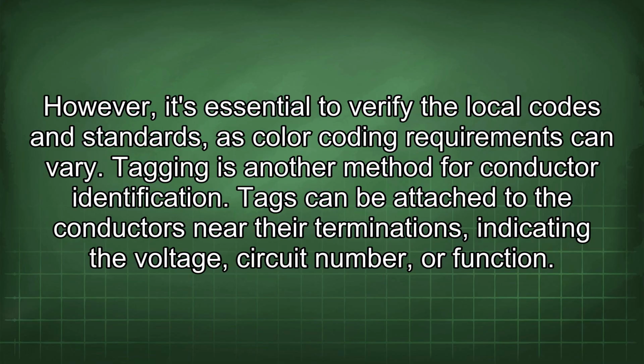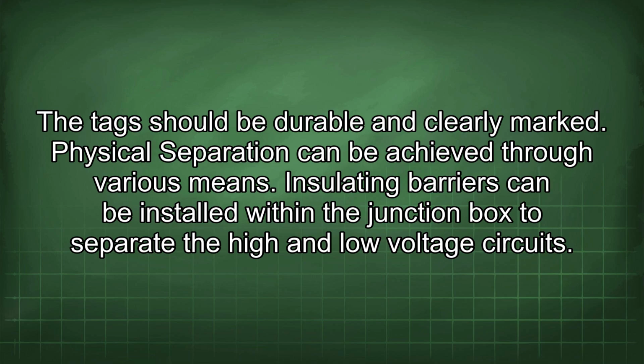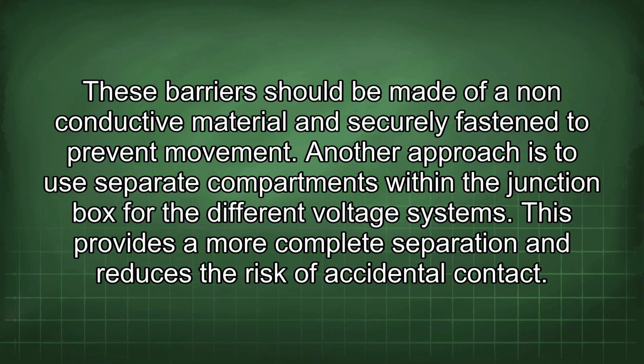Tagging is another method for conductor identification. Tags can be attached to the conductors near their terminations, indicating the voltage, circuit number, or function. The tags should be durable and clearly marked. Physical separation can be achieved through various means. Insulating barriers can be installed within the junction box to separate the high and low voltage circuits. These barriers should be made of a non-conductive material and securely fastened to prevent movement. Another approach is to use separate compartments within the junction box for the different voltage systems. This provides a more complete separation and reduces the risk of accidental contact.